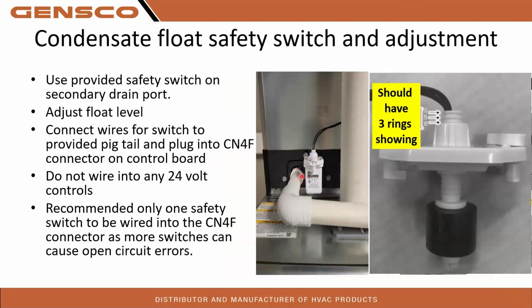So our coil, whether horizontal or vertical, you are going to have your primary drain on the left, secondary drain on the right. Your primary drain, just 3/4 inch PVC, just like a normal coil, nothing special there. And run that out to either your condensate pump or a drain or whatever you need to. This secondary switch does need to be adjusted. There's a height change for it. If you take it apart, there's this little nut right here. You want to make sure you have at least 3 rings showing above that nut in order for it to be properly adjusted.